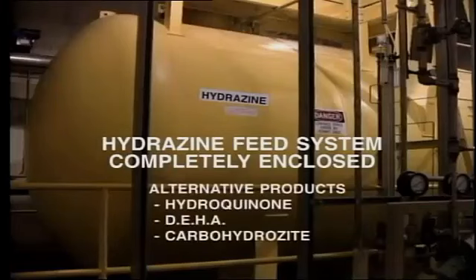Alternative products are available to be used in place of hydrazine, such as hydroquinone, DEHA, carbohydrazite, and others. These substitutes are apparently safer to handle. We have just mentioned that hydrazine volatilizes. Other volatile chemicals may be used in place of phosphate and caustic injection, where the boiler operating pressure is above about 1500 psi. The reason for this is that at high pressure, we wish to keep the solids content in the water as low as possible.